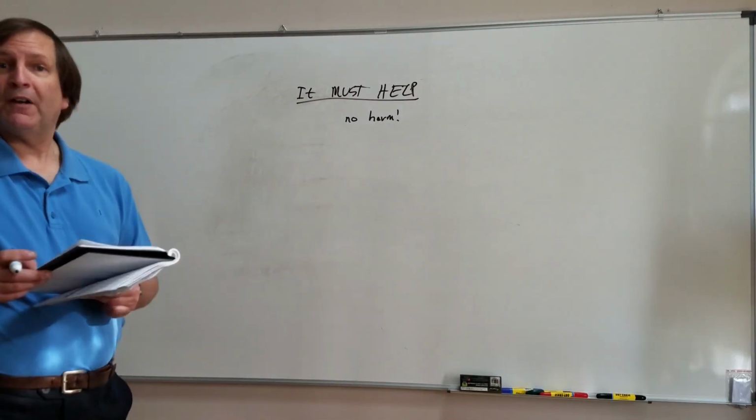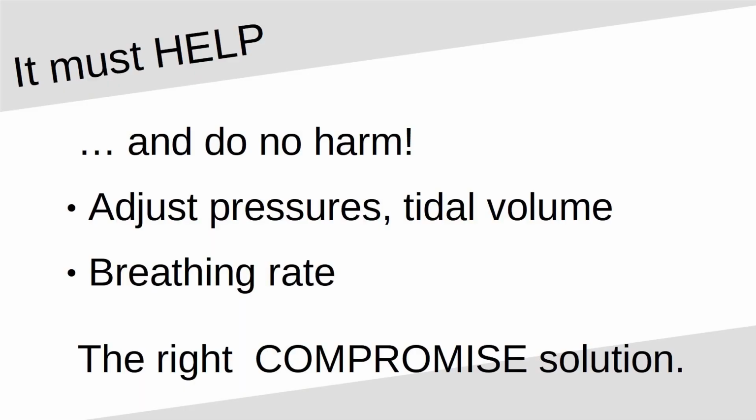The same thing applies to ventilators. You have to be very careful about the air pressures and tidal volumes you put into a human lung. Get it wrong, and you risk doing way more harm than good, or even seriously injuring the person. And that brings up one of the points that a lot of ventilators are missing.